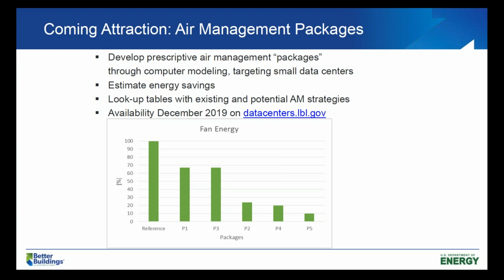And this fan energy performance is an example of how we can get that information out there. So the reference, you're using 100% of the fan energy, and then these 5 packages do a number of things that will reduce the amount of airflow needed and or improve the fan energy performance. And you can see the overall fan energy dropping to as much as 10% of the original energy.